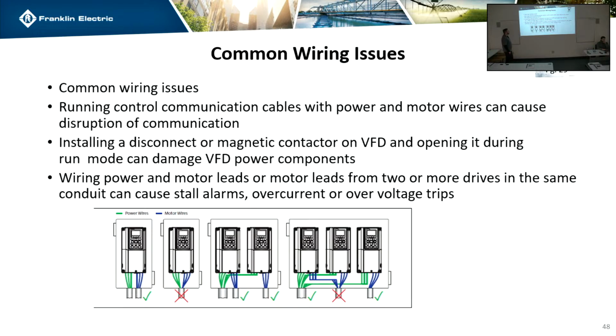So common wiring issues that you're going to see. This is for basically all VFDs. If you have your incoming power and your motor separate, it's fine. You're never going to have any problems. Don't combine them. We get it all the time. If you start getting over voltage faults and things like that, one of the things to look for is that you might see something that looks like this, but in 10 feet they've got a trough and it's all spaghettied together. The VFDs hate it, and you're going to get all sorts of nuisance tripping.